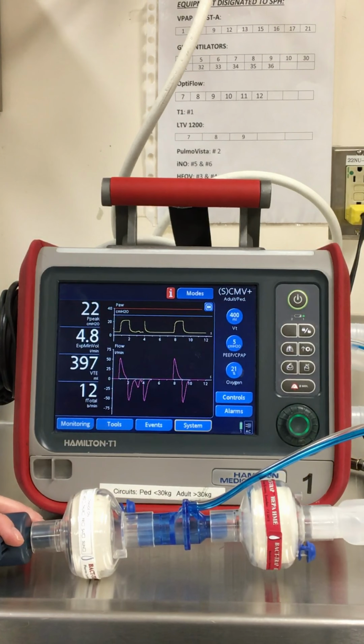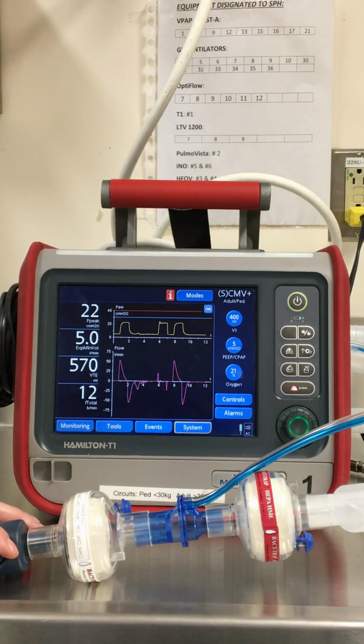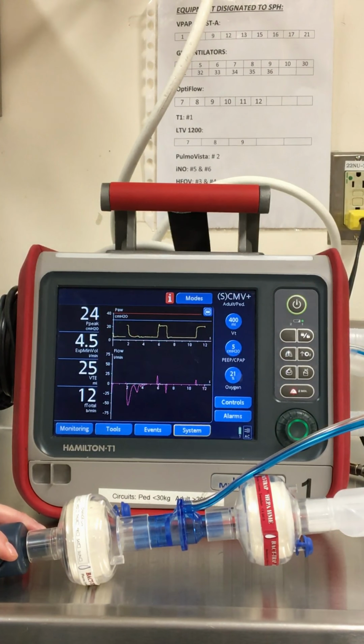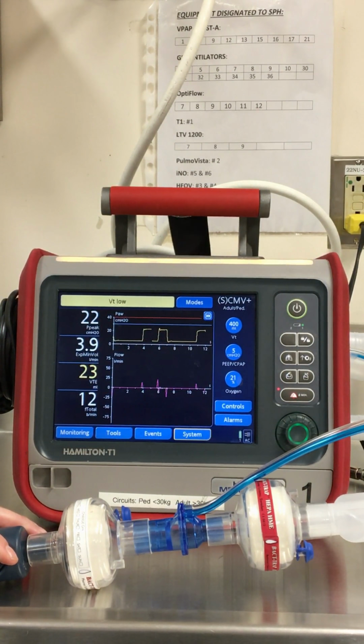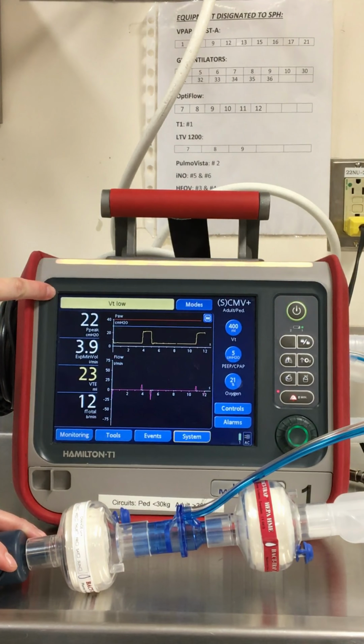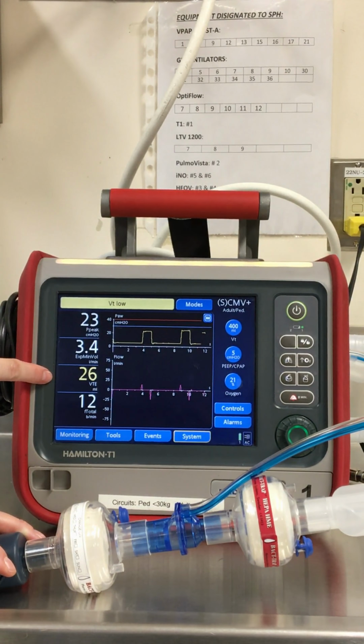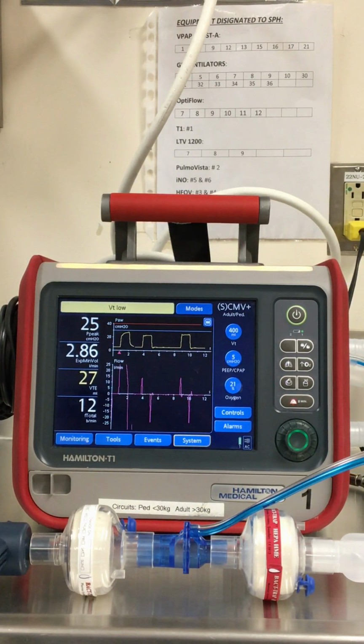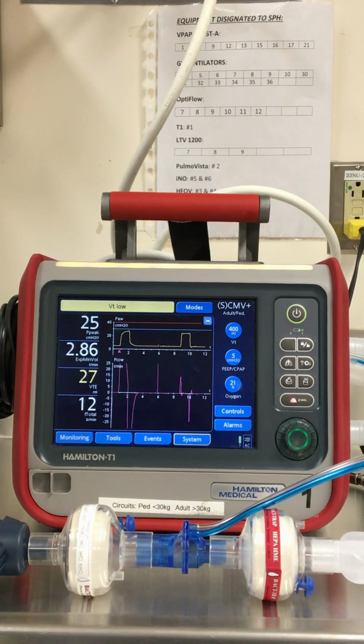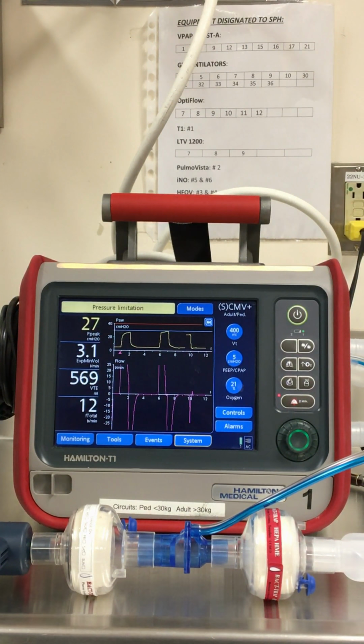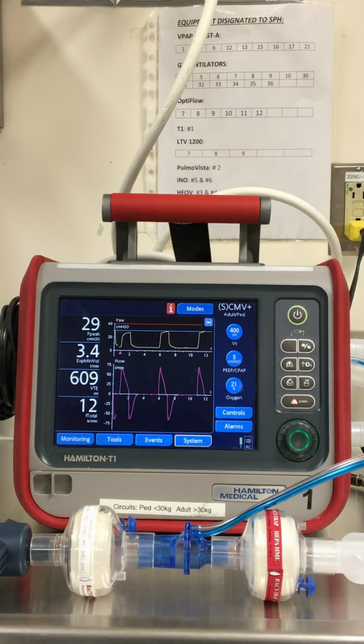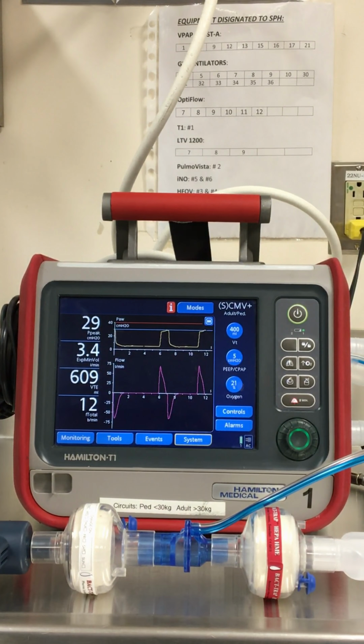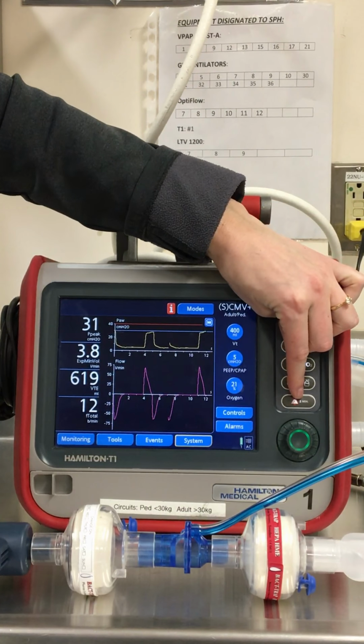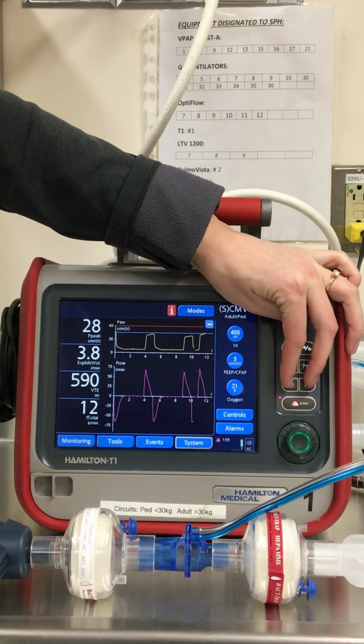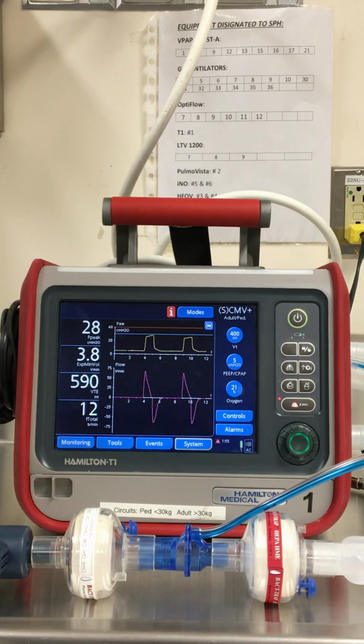All right, I will now try to show a low volume alarm. And there it is. You can see the yellow bar at the top, the yellow bar indicating tidal volume low, and our tidal volume that's located here in yellow now. Once the alarm has been fixed or the issue has been fixed, the ventilator will correct itself and come back to normal ventilation as it was previously set. And there we go. It's coming back to normal over a few breaths. As a reminder, you can use the silence button while you are troubleshooting. Press the silence once for 2 minutes of silence while you troubleshoot your alarm.